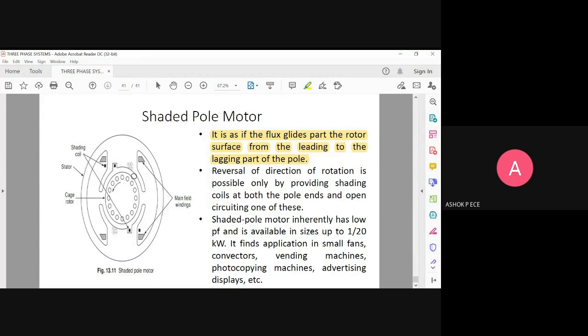For the reversal of direction — how to reverse the rotational direction of the rotor: the rotor rotates only in one direction (anti-clockwise). If you want to reverse the direction of rotation, you need to keep the shading coils at the other end and open circuit one of them. The reversal of direction of rotation is possible only by providing shading coils at both the pole ends and open circuiting one of these. I have four shading coils — one here, one here, one here, and one here — and by open circuiting one of them, it is going to provide a reversal in the direction of rotation.